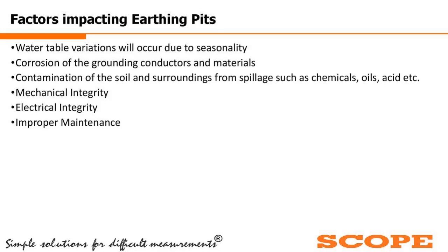Next, corrosion of the grounding conductors and materials. If corrosion happens at the grounding conductors and materials, then the contact with the earth surface changes, the resistance changes, and as a final result the earth pit resistance will change. Then contamination of the soil and surroundings from spillage such as chemicals, oil, acid, etc. Depending upon what type of chemicals or foreign materials enter the vicinity of the earth pit or the earth rod, the nature of the earth changes. As the nature changes, the conductivity or resistivity of the earth changes, and as a result the earth pit resistance changes.